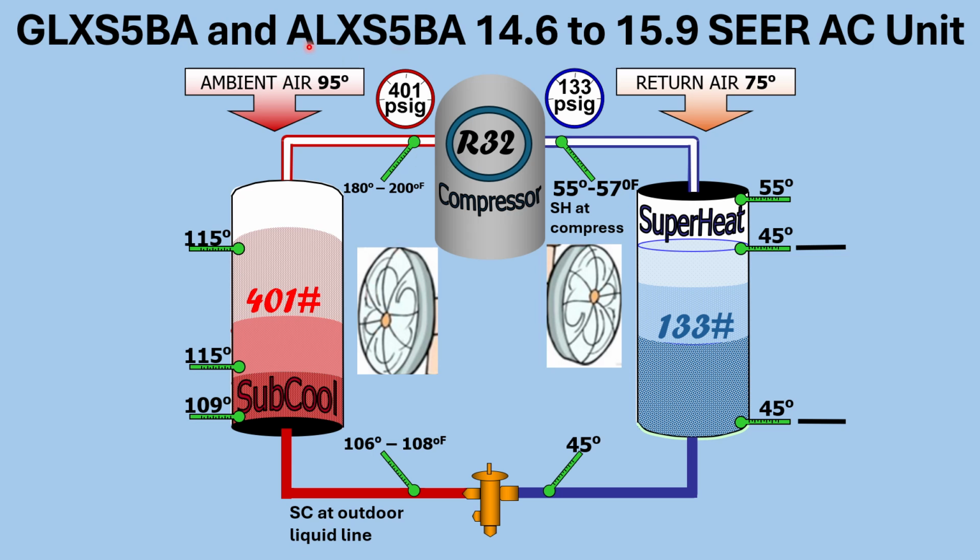So here we see an R32 example, and these are the units that these are for, and I'll show you the chart form in a minute. But pressure's a little bit different. Our operating temperatures are still pretty much the same, and the outdoor air temp and the return temp. But you do see a little bit higher discharge pressures here, and so that is a little bit of a difference there.